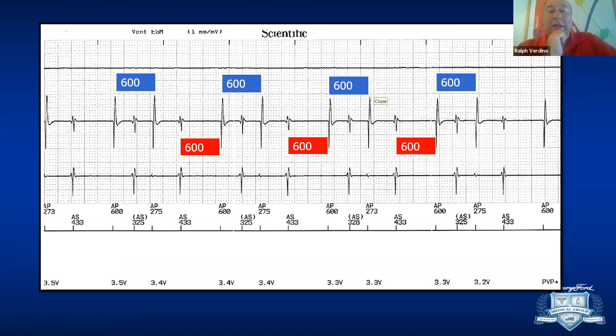Okay. So we have changing the rate, but we have decreasing the sensitivity. Okay. So changing the rate will not help because the faster the rate or the slower the rate, you will still sense the ventricular activity on the atrial channel. But yes, we have to decrease the sensitivity, which means you have to raise the fence so you don't see this far field in the atrial channel, and you can complete your threshold testing. Okay, so that's absolutely right. So this is an example of, again, oversensing or far field sensing.